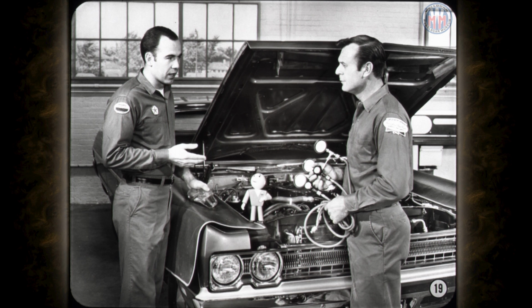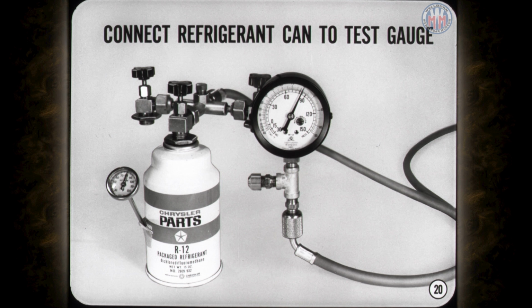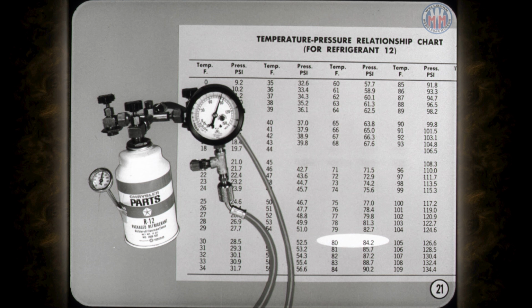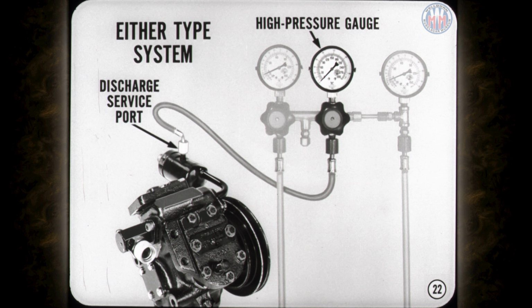Do you need a special tester to check gauge calibration? Nope. You can check the gauges by comparing their indications against the pressure-temperature relationship chart in the service manual. All you need is a nearly full can of refrigerant and an accurate thermometer. Tape the thermometer to the can so its thermal sensing element is below the liquid level. Then connect the refrigerant can to the hose of the gauge to be tested and purge the air from the hose. Put the whole rig somewhere overnight where the temperature is stable. In the morning, compare the thermometer and gauge readings against the service manual chart to check the accuracy of the gauge. Well, that sounds simple enough.